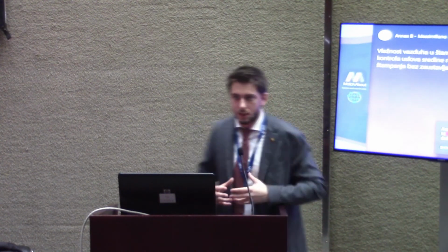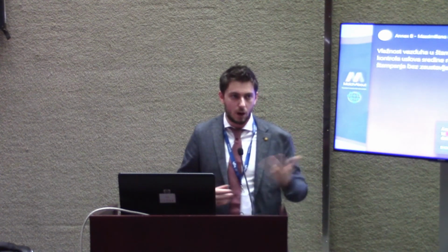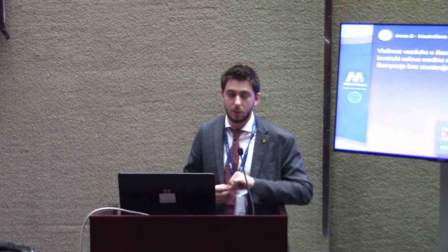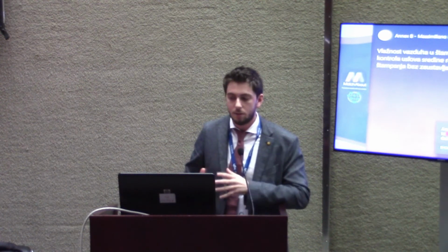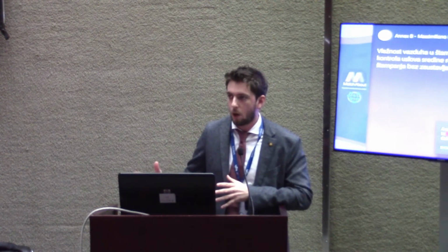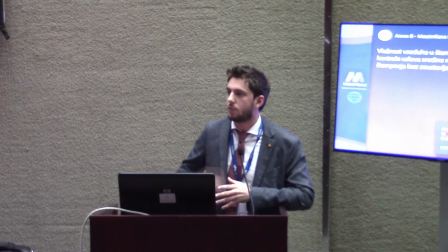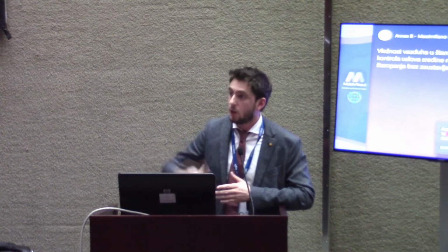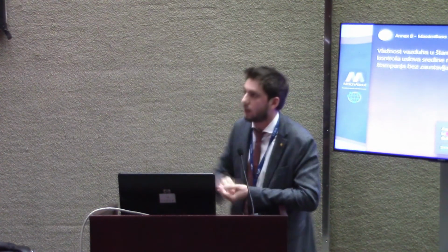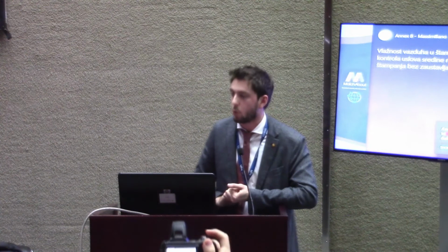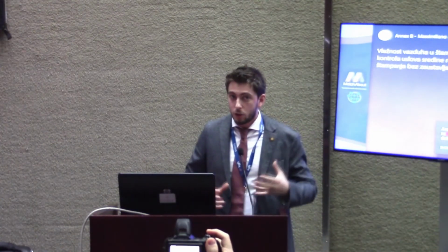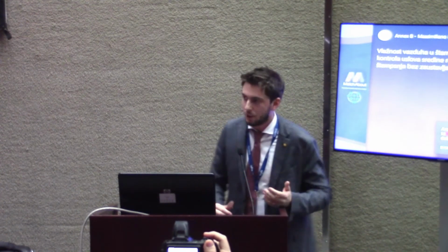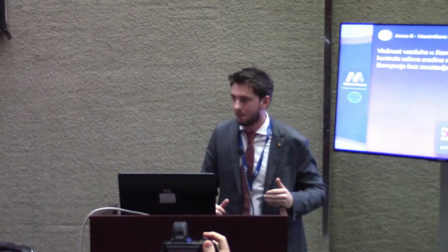A humidification system is made up of three main parts: a feed water treatment system, which is not always mandatory, a humidifier, and a distribution system. Of course, our goal is to keep the relative humidity of the environment as constant as possible, so that the moisture content of the paper will be constant, and so we will not end up with the defects I showed before. The humidification system can be installed in duct humidification or in direct room humidification.